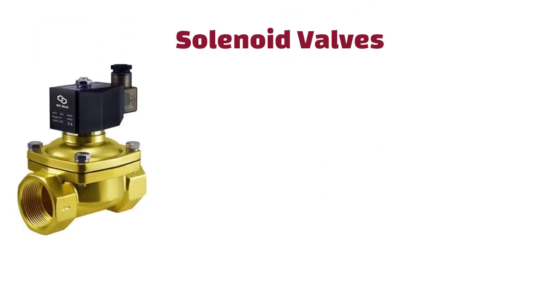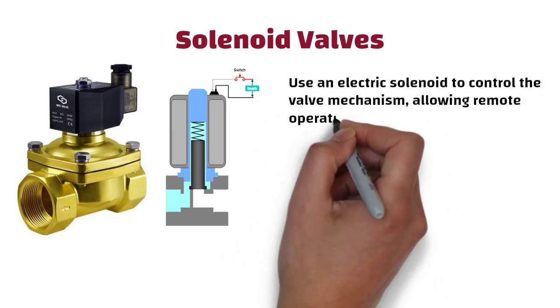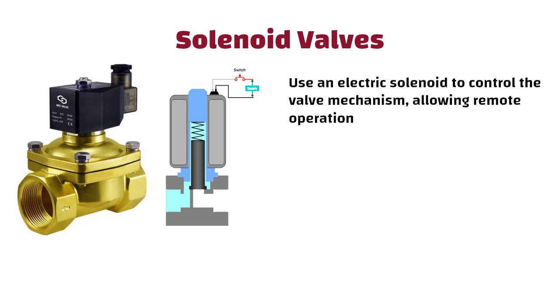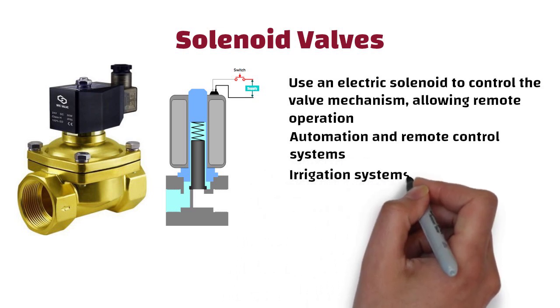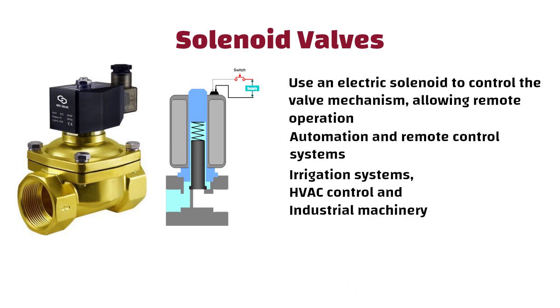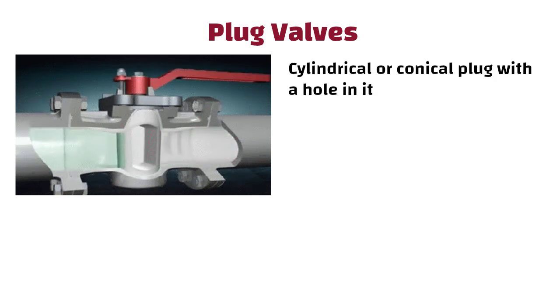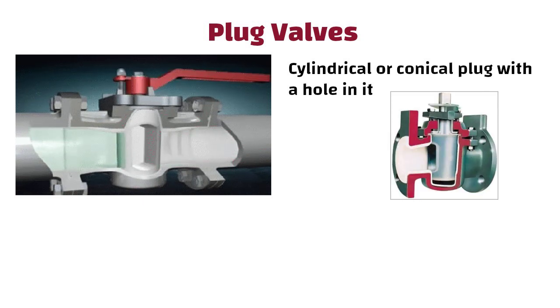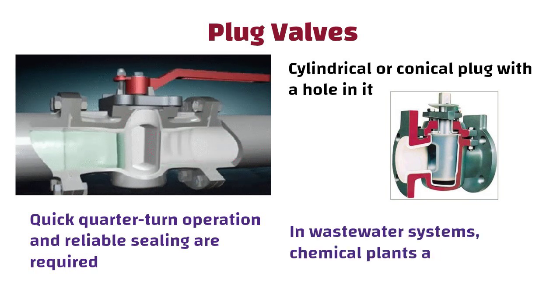Solenoid valves use an electronic solenoid to control the valve mechanism, allowing remote operation. These types of valves are commonly used in automation and remote control systems such as in irrigation systems, HVAC control and industrial machinery. Plug valves use a cylindrical or conical plug with a hole in it, which aligns with the flow path when open. This type of valve is used in applications where quick quarter-turn operation and reliable sealing are required, such as in wastewater systems, chemical plants and oil refineries.